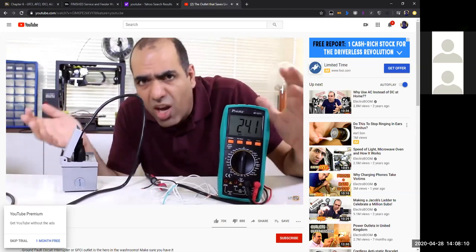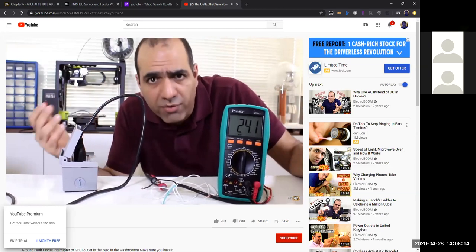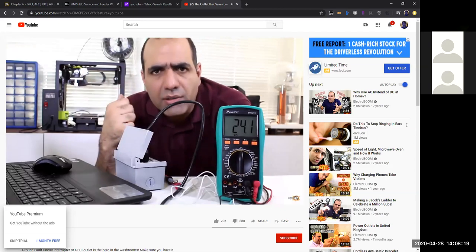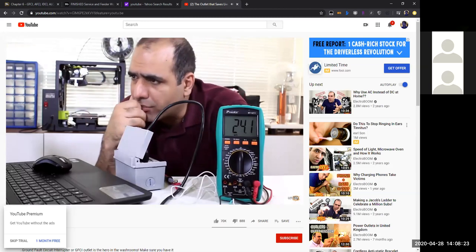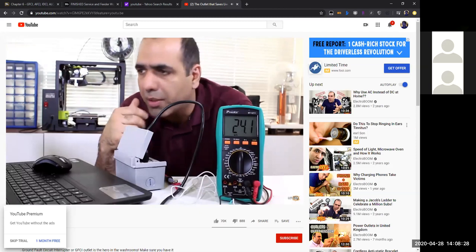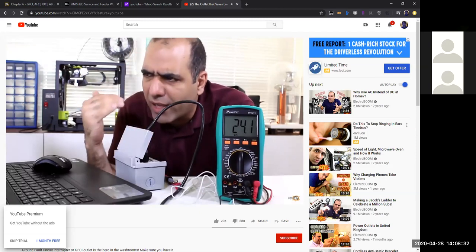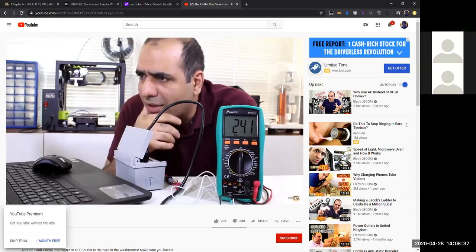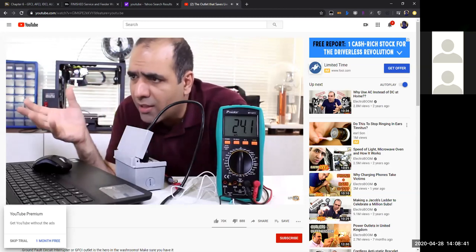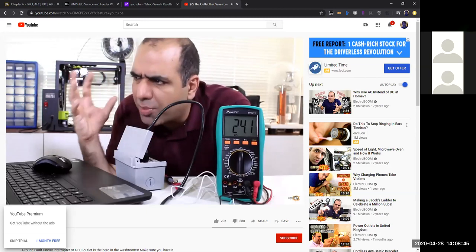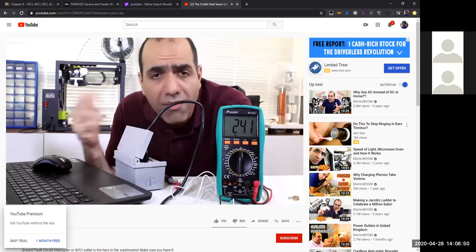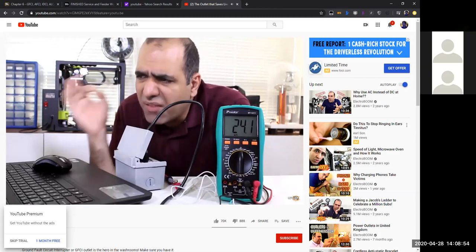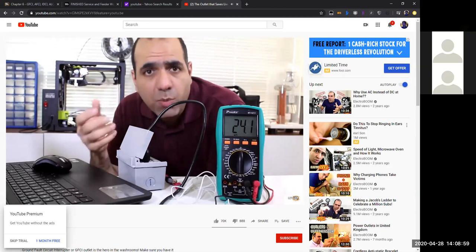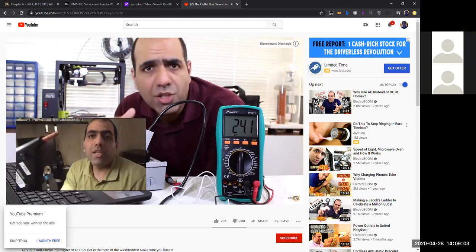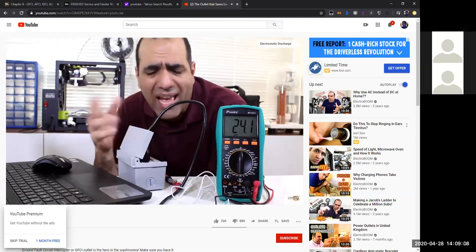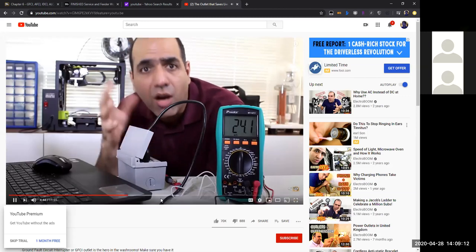Again, it doesn't pop if your body is between live and neutral, it will look like a normal circuit. It only pops for currents over 5 milliamps between live and earth. I think 5 milliamp is a pretty high and dangerous current, but according to information, you start sensing electricity around 1 milliamp. I personally start sensing it around half a milliamp. 1 milliamp is pretty painful for me. As it goes up around 10 milliamps, it becomes extremely painful and can cause severe shock, muscle paralysis, and death. At 10 milliamp and higher, you won't be able to let go, which results in extended exposure to electricity that would result in death. Closer to 100 milliamp, it becomes very hard to breathe and there is irregular heartbeat that would easily end your life. Above 100 milliamp, you die. Breathing stops completely and there will be severe burning as an added bonus. Of course, all this depends on the length of exposure to high current. For example, in case of a 25 kilovolt electrostatic discharge, the current through the body is way more than 1 amp for around a microsecond, but that doesn't affect a healthy person. But if it's a fixed high voltage supply creating high current, you won't be able to let go.